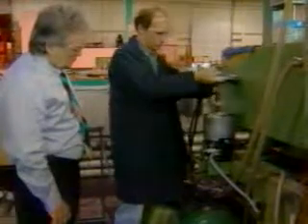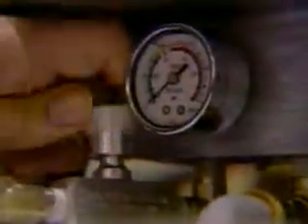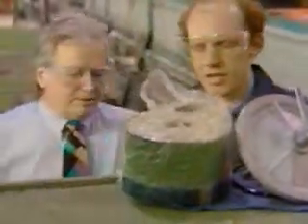I was concerned about how often we'd have to change elements and how long we'd be shut down during the process. Triple R has that covered, Tom assured me, as he broke the vacuum seal on a new replacement filter. Earlier, Tom had turned off a needle valve at the T-tap to isolate the unit from the rest of the hydraulic system. He explained that when the needle valve is turned off, there's never any downtime while changing or inspecting the element. After the initial cleanup period, the element will only need to be replaced 2 or 3 times a year. Triple R has built in a quick and clean method for removal. The whole procedure takes only a couple of minutes.